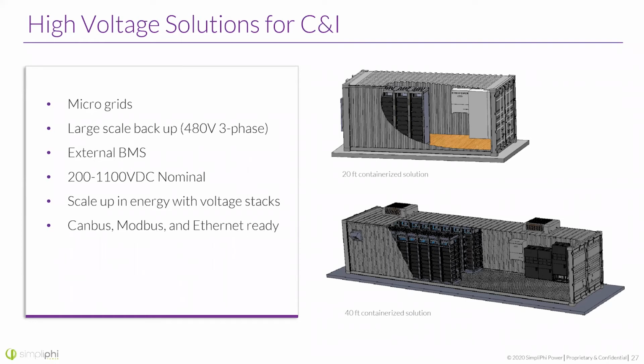The BMS is actually CAN bus, Modbus, and Ethernet ready right out of the gate, so it has that high level communication typically required on these big projects. It also has its own monitoring system built in, with different faults, self-clearing faults versus non-self-clearing faults, and triggers and alarms.